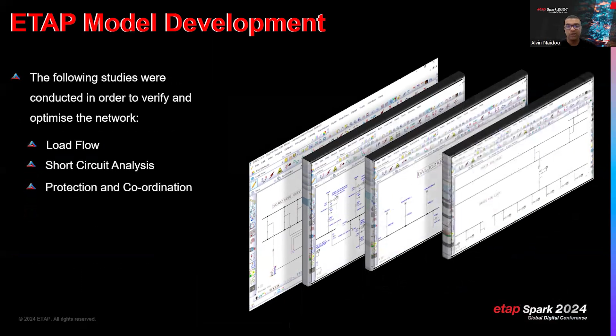Due to the hybrid nature of the network with both new and legacy technologies, it was decided that for all new-ish types of substations, the IEC 61850 communication protocol would be the medium of choice between the IEDs and the RTUs. From the RTUs to the master station, we would use IEC 60870-5-104. At substations where legacy equipment was still in operation, we opted for Modbus RTU and the hardwiring of contacts with the appropriate voltage polarization.